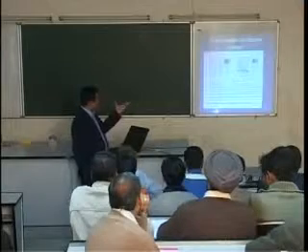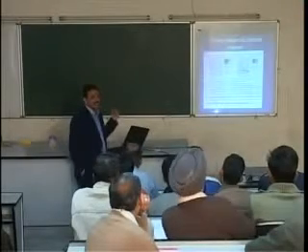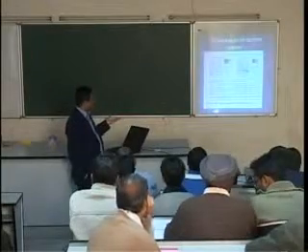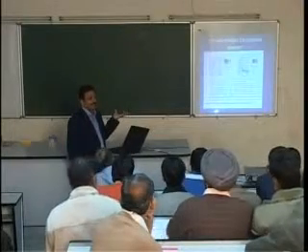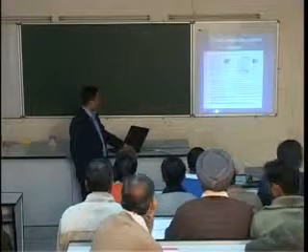These are a few slides I have taken from the manuals of the vector network analyzer, where they give the difference between the network analyzer and the spectrum analyzer. The spectrum analyzer shows single-signal amplitude characteristics, what type of sidebands or harmonics are present, because in active devices there may be second or third harmonics. One can also demodulate complex signals. In both cases we have a tuned receiver inside, whether it is a spectrum analyzer or a network analyzer. We need a detector or a receiver. Because receivers are generally more sensitive, one can design the receiver in such a way that it has more bandwidth and more dynamic range available.